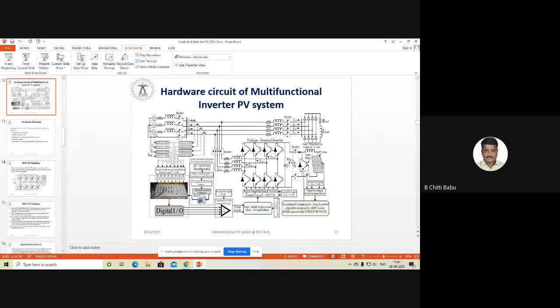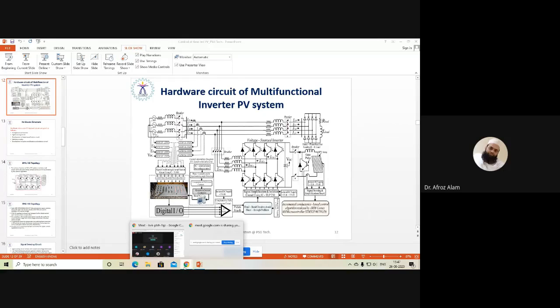Thank you, sir. Or instead you can connect a three-phase star-delta transformer instead of the neutral wire. Here you connect the star-delta transformer, and the secondary is delta. As it is a closed delta, it will take care of the third harmonic, so it will not interact. Okay, thank you, sir.